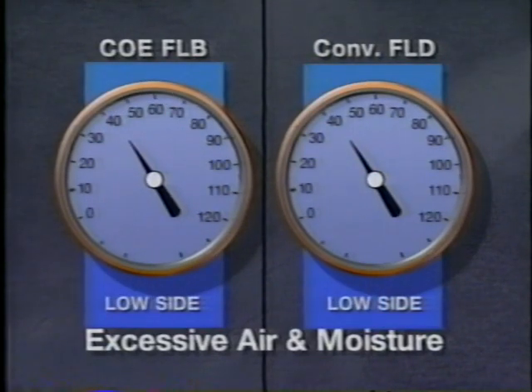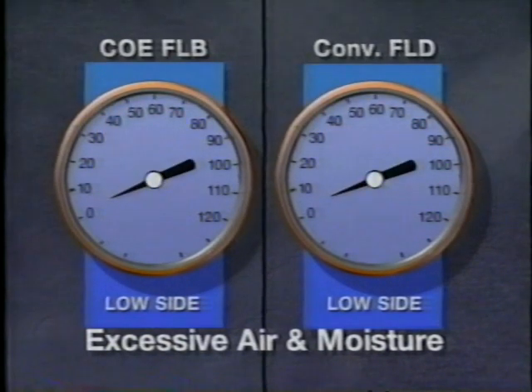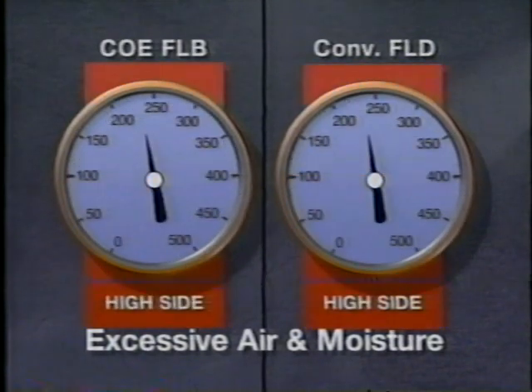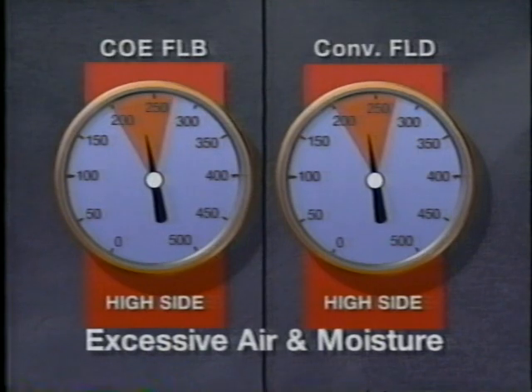If there is excessive air and moisture in the system, the suction pressure will be high at first, then drop to a lower range or indicate a vacuum as the system runs. The discharge pressure will run high. Any leaks will have to be repaired, and the system will require purging or flushing.